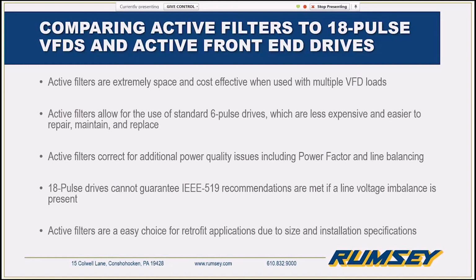We can correct for other power quality issues, and with 18 pulse drives, there are many different white papers about this, but 18 pulse drives struggle if there's a line imbalance present from the utility already. And that's often the case in the real world. So 18 pulse drives struggle more often to meet the 5% specification.